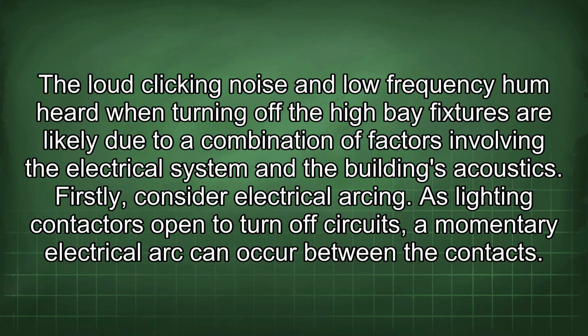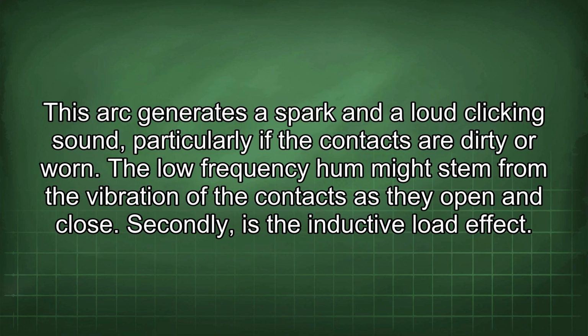The loud clicking noise and low-frequency hum heard when turning off the high bay fixtures are likely due to a combination of factors involving the electrical system and the building's acoustics. Firstly, consider electrical arcing. As lighting contactors open to turn off circuits, a momentary electrical arc can occur between the contacts. This arc generates a spark and a loud clicking sound, particularly if the contacts are dirty or worn. The low-frequency hum might stem from the vibration of the contacts as they open and close.